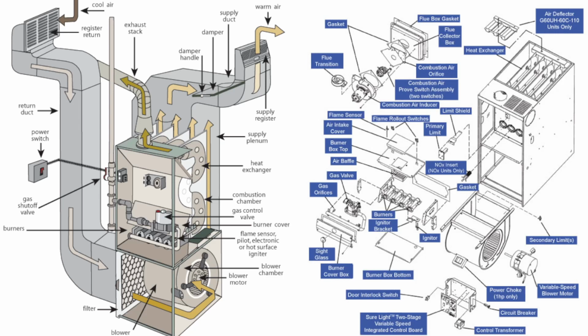You have across your burners, and if you see where the arrow is, you will see where the burners are. There are 4 of those in this one. Some, depending on the BTU that it is putting out, could have more than 4. As you are going down, you will see where the filter base is. Nowadays, we have filter racks, and they'll have one of these filter racks that would mount to the side over there, and you would drill it in with 1/4-inch self-tapping screws and then seal it in with some silver tape and some mastic if you choose. That allows the homeowner to change the filter on a 30-day basis, or sooner if need be.